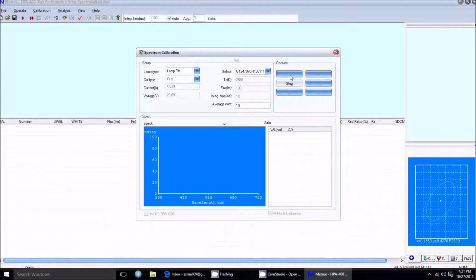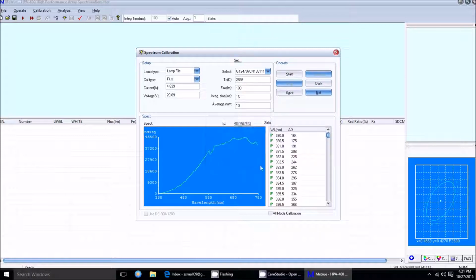And I can hear the HPA running, and it will stop and finish when it's done on its own. You don't need to hit the stop button. You just need to let it do its thing. Oh, I did make one mistake. I am going to stop it, because that was a good note so that you don't make the same mistake in the future. It has to run through its filters, calibration complete. It's not actually. I need to hit all mode calibration here. Now I can start. And again, it will stop when it's done.